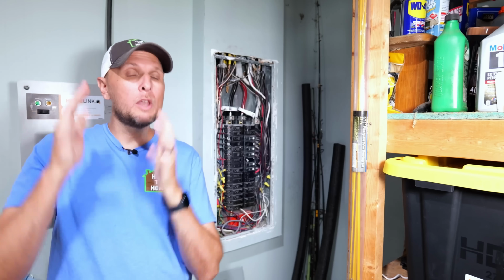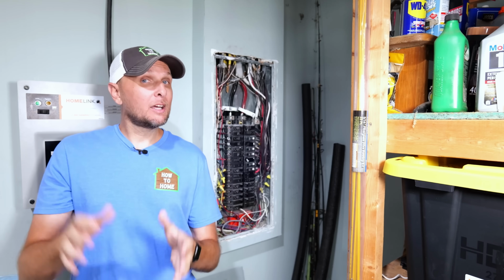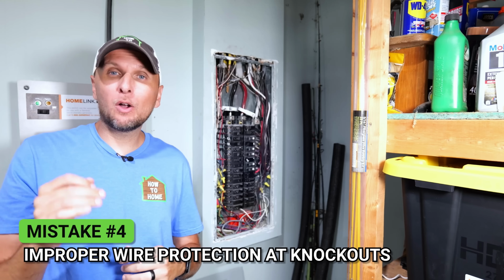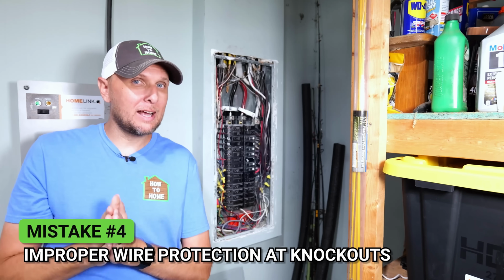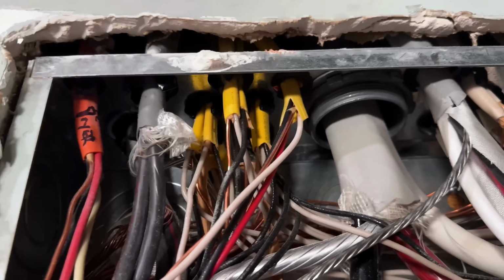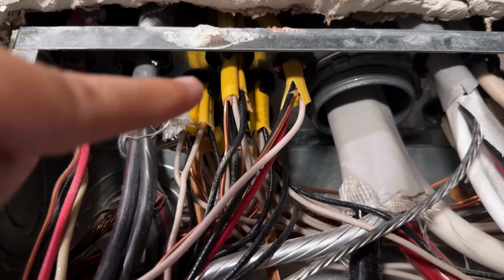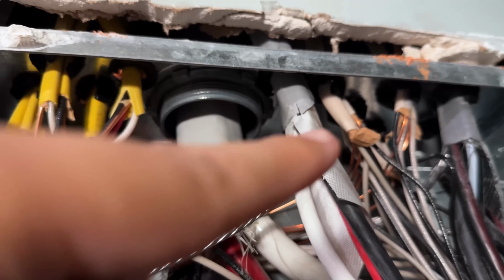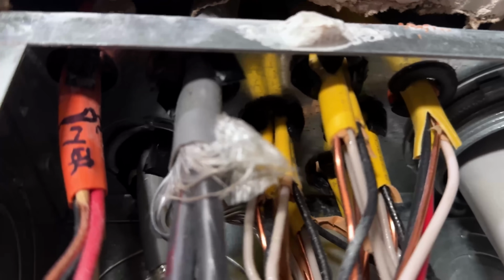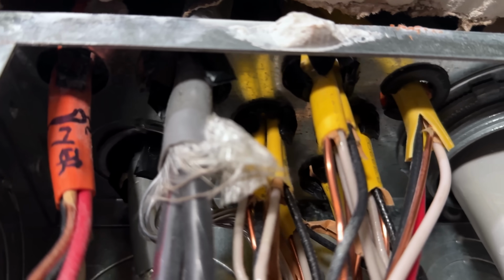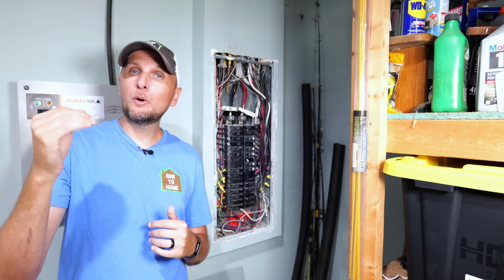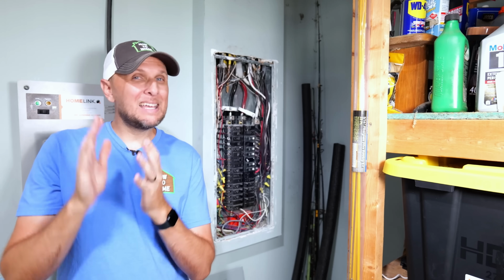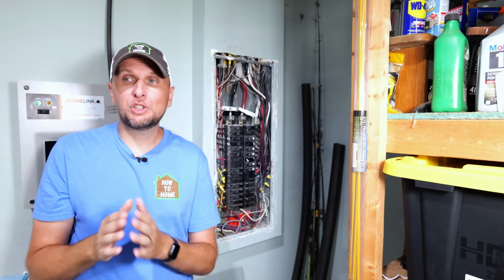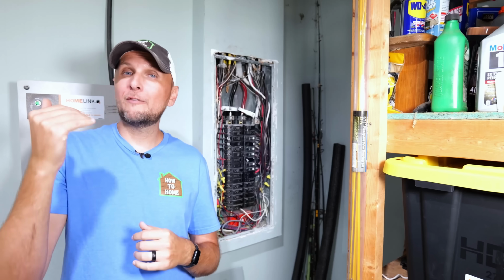Another big mistake a lot of people make comes down to the wires entering the panel not having proper connectors on them. What do I mean by connectors? I'm talking about where the wires are coming in—there should be some sort of connector protecting the wires or cabling coming through. The reason is those sharp knockout edges can easily cut through wiring insulation, which can lead to shorts or even faults.